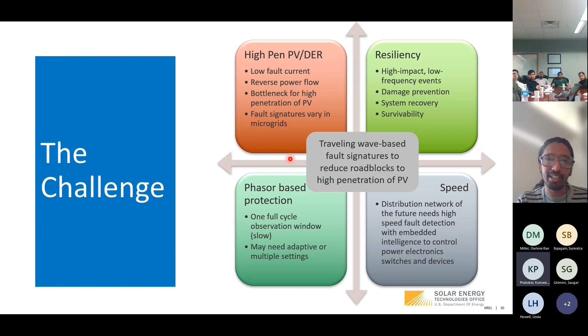The first step is sort of like the low TRL. We took the idea from the paper, because from physics we know that when there is a fault, it generates a traveling wave, and if you can see it, you can backtrack using the speed of light and the network structure to detect it. That was considered very low TRL, and we ran software simulation in EMT using EMTP-RV, showcasing how this behaves in a transmission system and a distribution system, and whether it actually exists and can be seen.